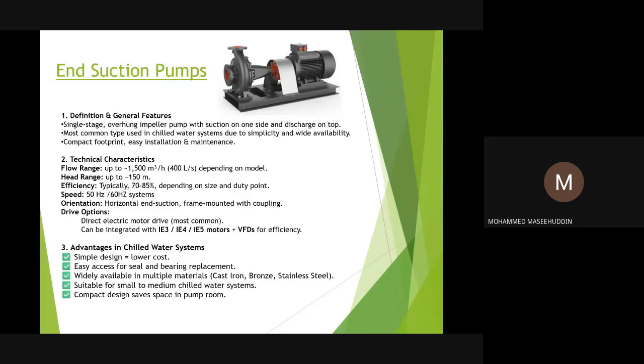Now, when we spoke about the end suction pumps, which are used mostly in the primary circuit of the chill water segment, this is the kind of pump we're talking about, which is also called BPO, back pull-out type, where without disturbing the piping connections, you can easily do the maintenance of the pump by replacing the seals, bearings, shafts, etc. And this type of pump caters to a capacity of up to 400 liters per second and head up to 150 meters. Of course, the efficiency typically depends on the type of pump being selected, and it really depends on the duty conditions as well. The best optimum duty conditions will get the best optimum efficiencies within the pump itself. But typically it ranges between 70 to 85% efficiency.